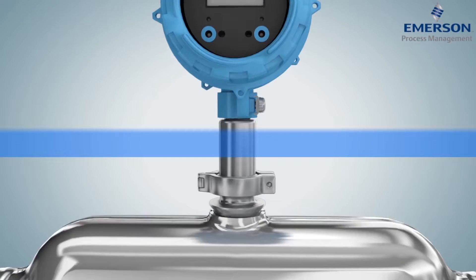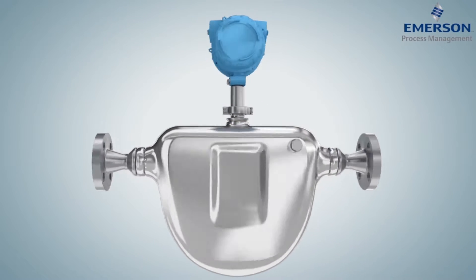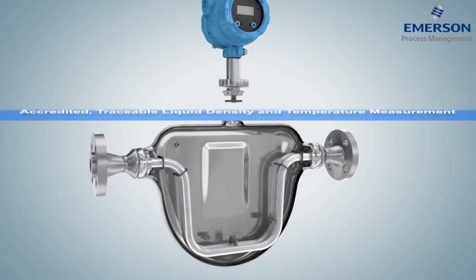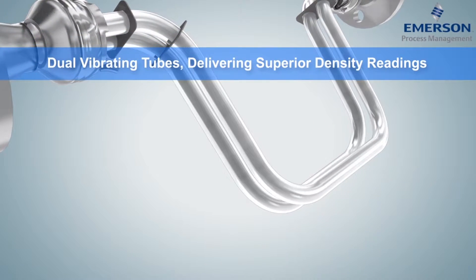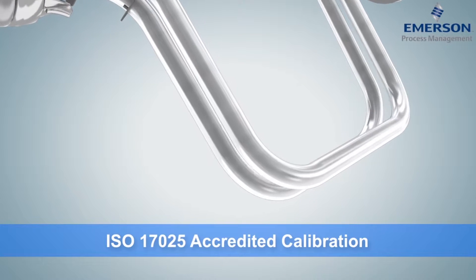Through simple harmonic motion, Micro Motion's Peak Performance Compact Density Meter, or CDM, guarantees accredited traceable liquid density, temperature, and concentration measurements of high-value products. The natural frequency of the CDM's dual-vibrating tubes provides superior density readings, while liquid flow rate is indicated by the twist.